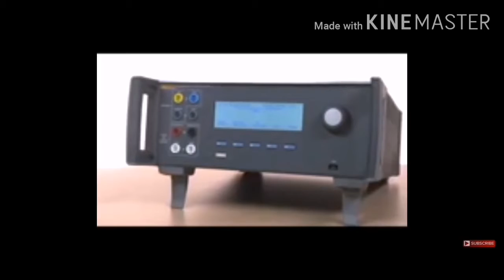Everything you need to test all critical functions of today's high-power electrosurgical units is either integrated into the design or included with the unit. There's no need for extra cables, leads, or switch boxes to test precision power, current, frequency, crest factor, and load resistance ranges. The state-of-the-art technology of the QA-ES3 provides exceptional accuracy and range of measurement. Its wide range of loads allows users to test the breadth of electrosurgical generators.